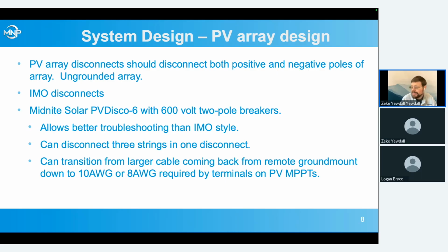There's kind of 2 options for these external disconnects that disconnect both poles. If it's just one string, you can use 2 poles of the old 600 volt Square D knife blade type switch. But there are some newer and cheaper options, especially to do more than just 2 poles at once. Because say you've got several strings. One of these is the IMO. There's a bunch of different distributors carrying the IMO disconnects. They work fine. They look a lot like the little twist switch that was on the bottom of the old SMA string inverters, possibly exactly the same internally.